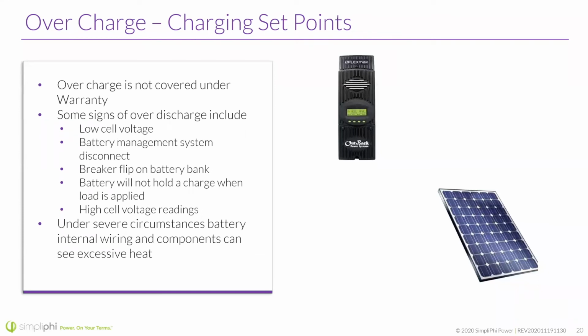Okay, so overcharge is not covered under warranty. It's important to note that some signs of, that's a typo there, overcharge, and maybe it's a good typo because the signs are basically the same. So it's important to understand the signs of over discharge and overcharge can be very similar. They can include low cell voltage, as I mentioned earlier, battery management system disconnect. Again, that's not the breaker flipping, that's the internal circuit. The breaker flip on the battery bank, though, battery will not hold a charge when load is applied. And one that's a little different than discharge signs is the high cell voltage readings.